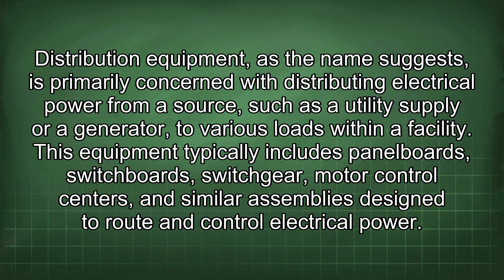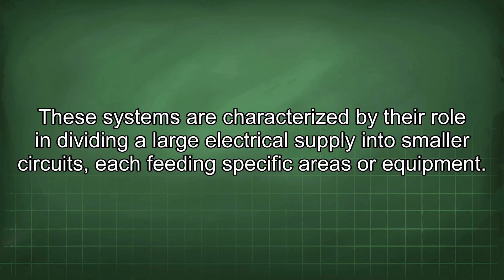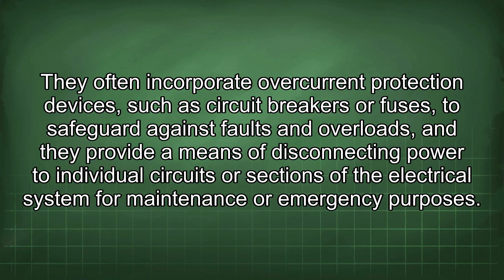This equipment typically includes panel boards, switchboards, switchgear, motor control centers, and similar assemblies designed to route and control electrical power. These systems are characterized by their role in dividing a large electrical supply into smaller circuits, each feeding specific areas or equipment.